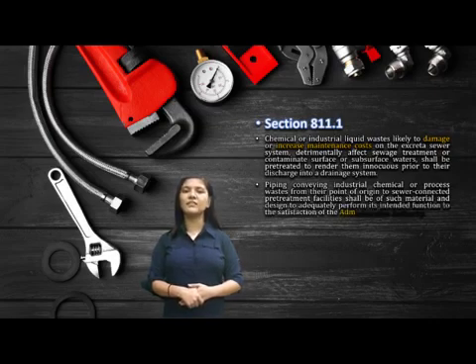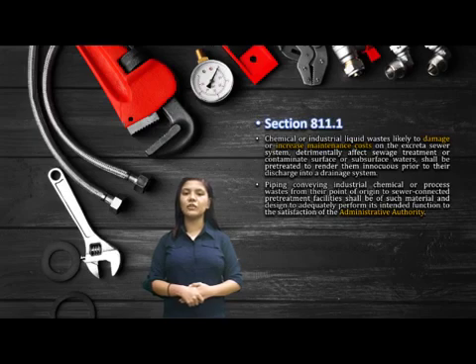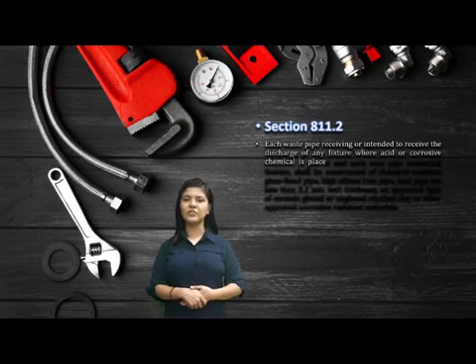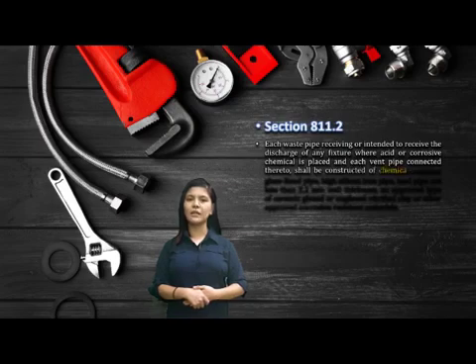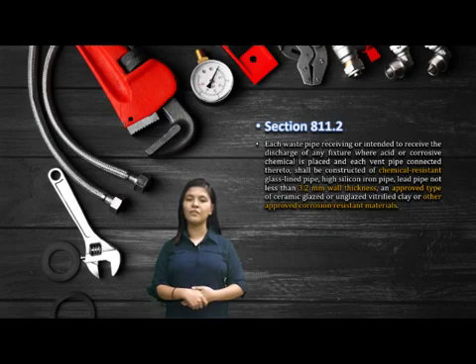Piping conveying chemical or processed waste from their point of origin to sewer-connected pre-treatment facilities shall be of such material and design to adequately perform the intended function to the satisfaction of the Administrative Authority. Section 811.2: Each waste pipe receiving or intended to receive the discharge of any fixture where acid or corrosive chemicals are used, and each vent pipe connected thereto, shall be constructed of chemical-resistant glass-lined pipe, high-silicon iron pipe, lead pipe not less than 3.2 mm wall thickness, or an approved type of ceramic-glazed or unglazed vitrified clay, or other approved corrosion-resistant materials.